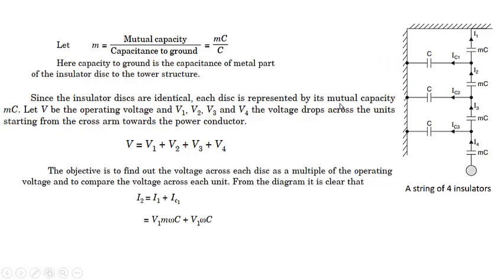Now let us try to see what will happen to the voltage distribution. We have a string of 4 insulators. This actually shows an insulator. It is the upper pin of the insulator. This is the lower pin where the conductor is connected, and this is another insulator. This pin is connected to another groove of this insulator. So we can show that each insulator will behave as a capacitor, and these 4 insulators will be capacitances which are connected in series. And there will be one more. This is actually a tower structure.